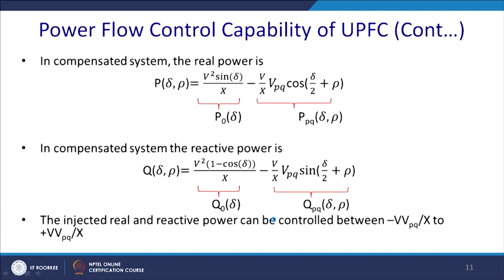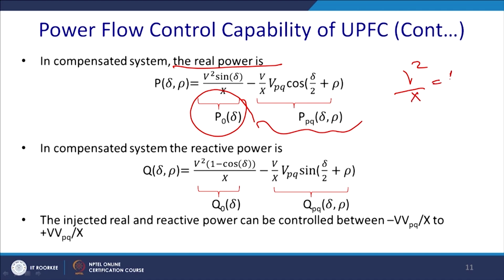So, we can see that for the compensation system, the real power is now a function of rho and delta. It is V square by x sin delta, which is the uncompensated one, and thereafter you have a compensated one, where V V_pq by x cos(delta by 2 plus rho). Where V square by x is 1, we generally consider V V_pq by x as 0.5. This is something we will assume, and we will consider this as the radius of the circle, and that is your sphere of influence of this kind of UPFC.